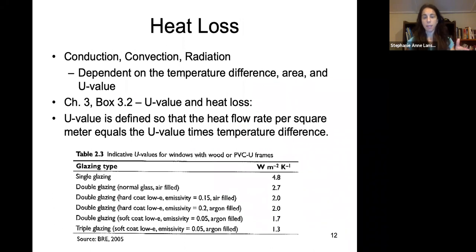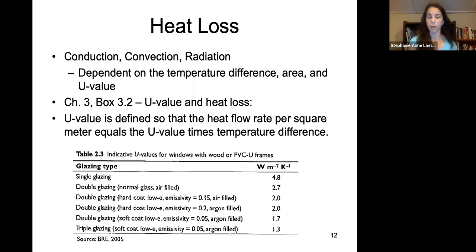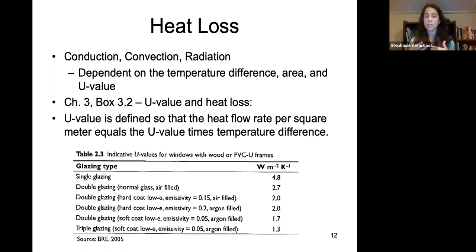Heat loss depends on conduction, convection, and radiation, and is dependent on the temperature difference, the area, and the U-value. There is a full section on U-value and heat loss in your textbook. If you have a single-glazed window, your watts per meter squared per Kelvin will be much higher than if you have triple glazing. The heat flow per square meter equals the U-value times the temperature difference, so you will have less heat going through triple glazing than single glazing.